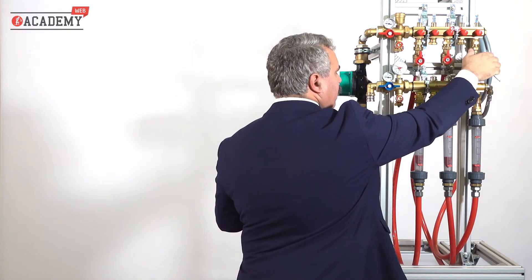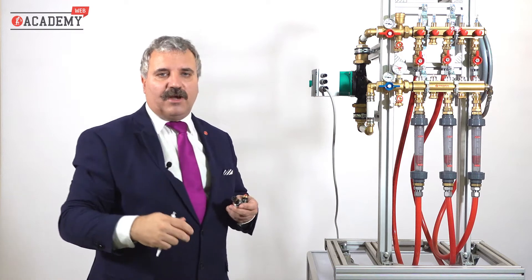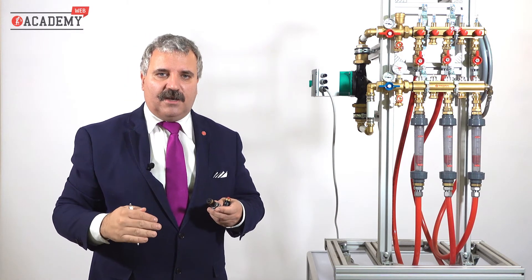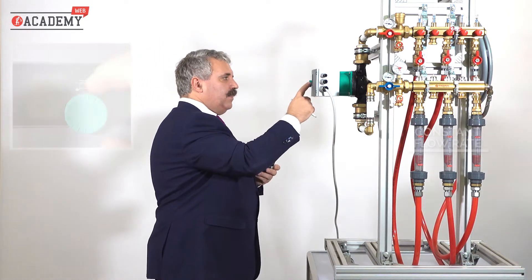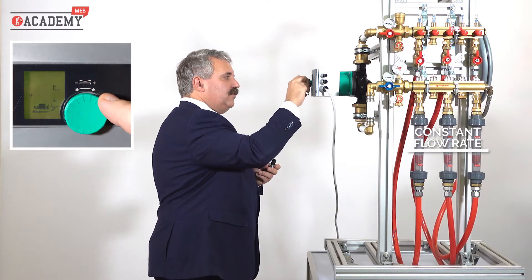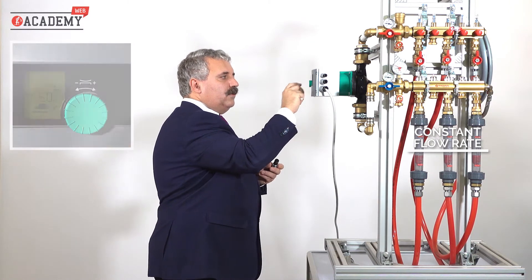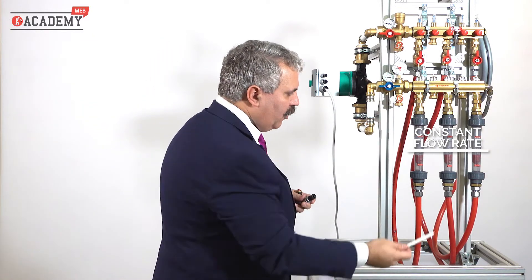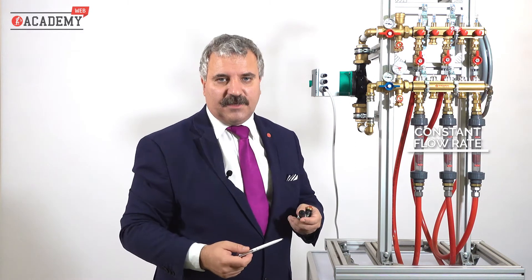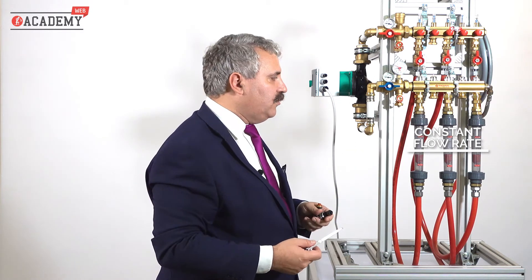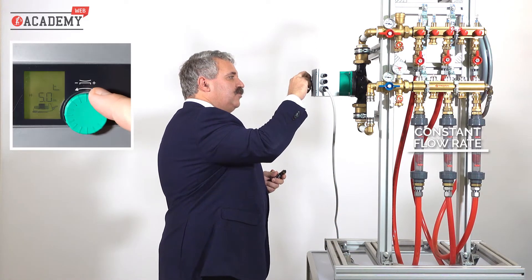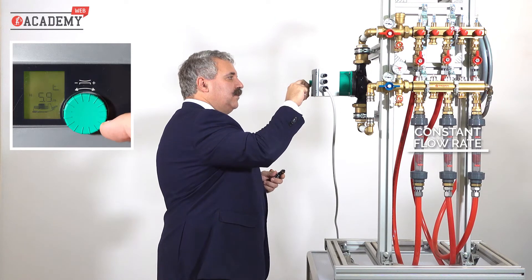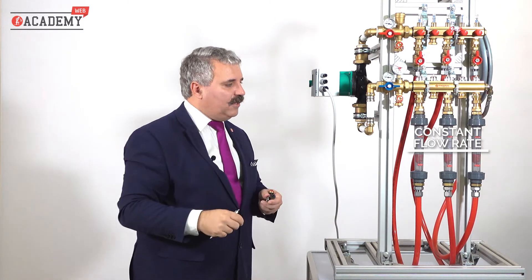Now let's see what happens when we modify the differential pressure. This is what you can experience in an installation with several manifolds or different thermal loads. We increase the differential pressure to 50 kilopascal. As you can see, the cartridges have been able to manage this increase. And finally, let's bring it to the maximum differential pressure, 60 kilopascal. Again, all flow rates remain constant.